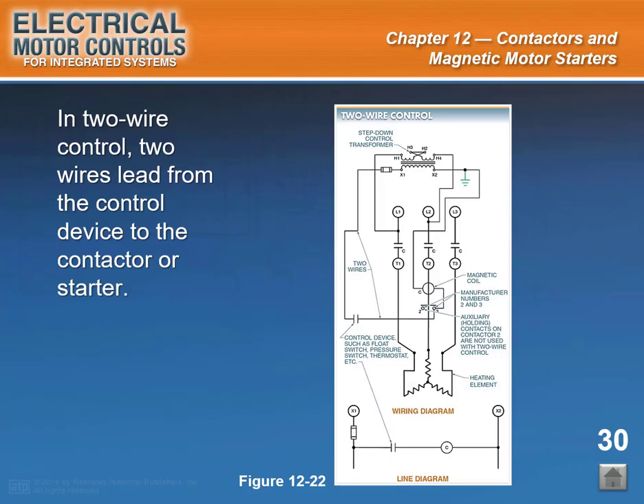Slide caption: in two-wire control, two wires lead from the control device to the contactor or starter. See Figure 12-22. The control device could be a thermostat, float switch, or other contact device. When the contacts of the control device close, they complete the coil circuit of the contactor, causing it to energize. This connects the load to the line through the power contacts.